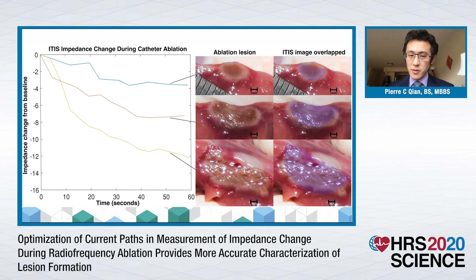While our data is insufficient to analyze detection of tissue overheating, given that only 1 steam pop occurred, it is nonetheless interesting to note that the ITIS impedance tracing during this ablation showed an impedance fall of approximately 15 ohms before a transient impedance rise, which was associated with the steam pop. This drop in impedance was very large, given that the upper quartile for ITIS impedance was only 8.3 ohms.